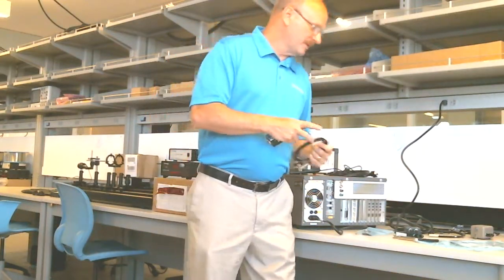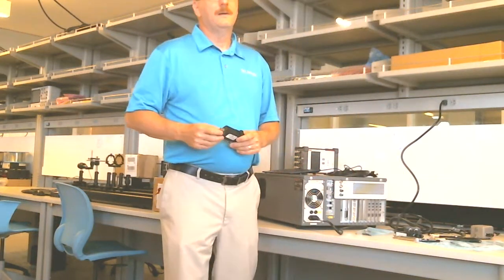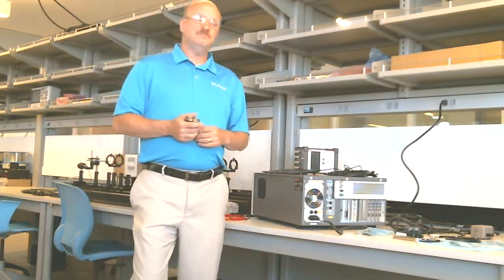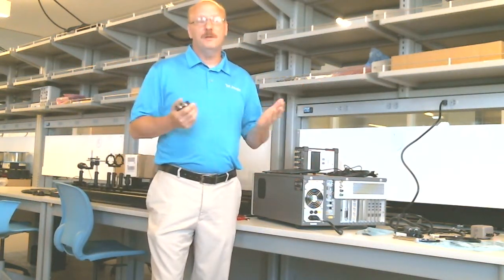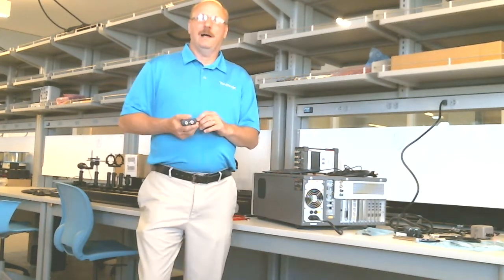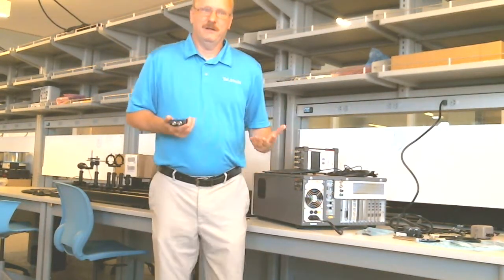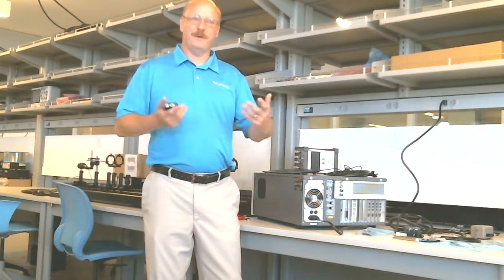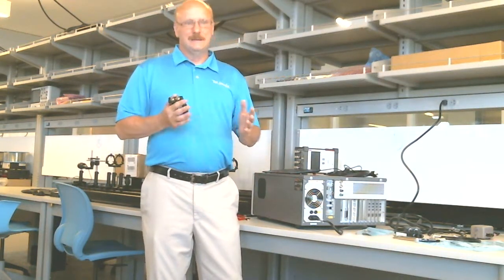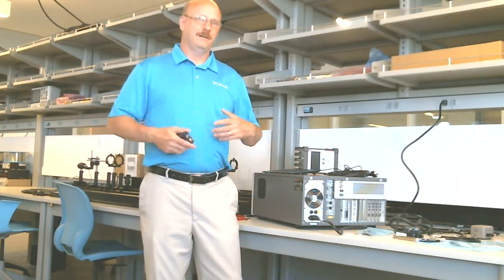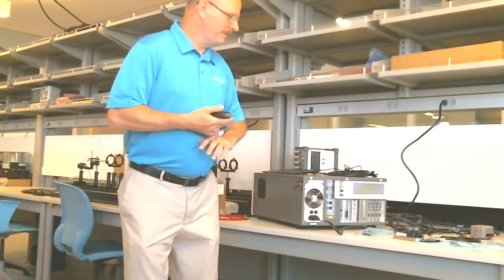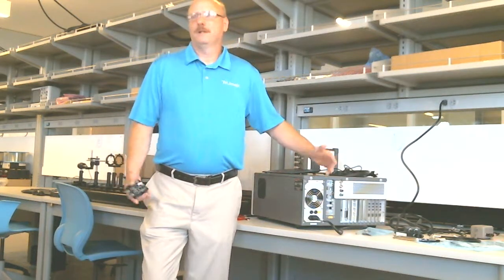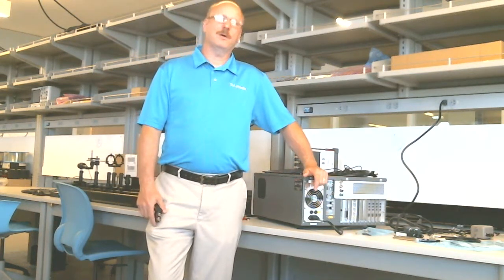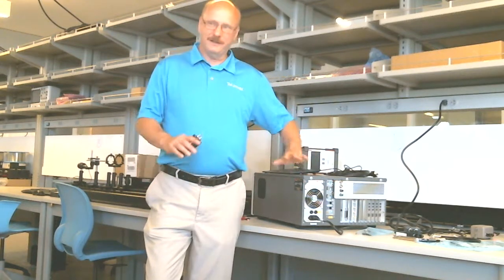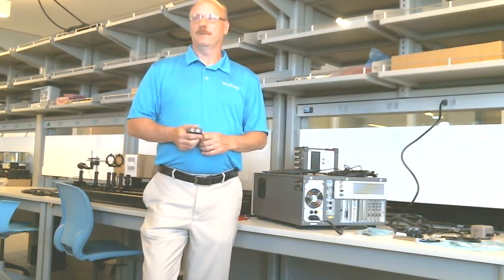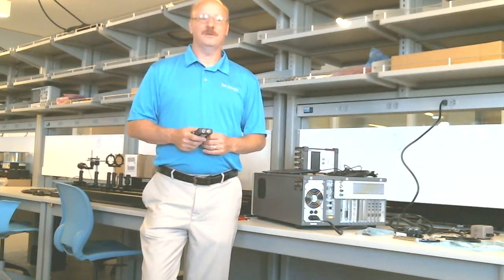We recommend 1 year for calibration, but when you calibrate is really up to you. It depends on what type of measurements you're making. If you're making nano-amp or femtoamp measurements regularly, you might want to calibrate as frequently as possible. But if you're making microamp measurements, you'll probably be fine for a couple of years. Either way, we recommend 1 year, but ultimately that's your decision.